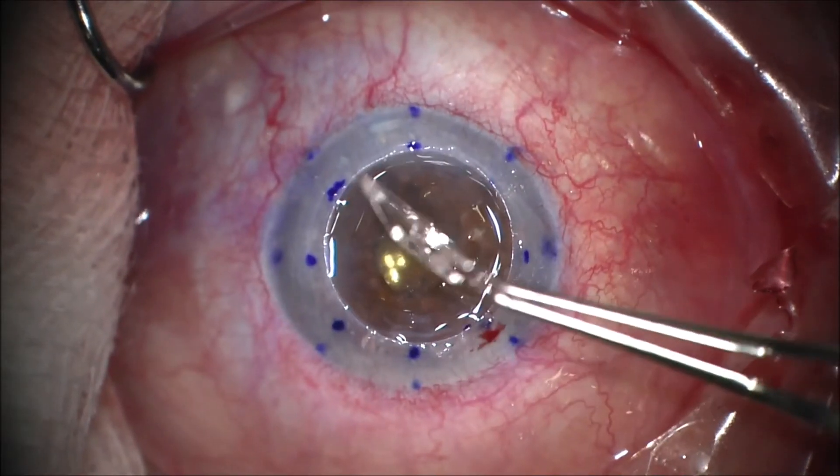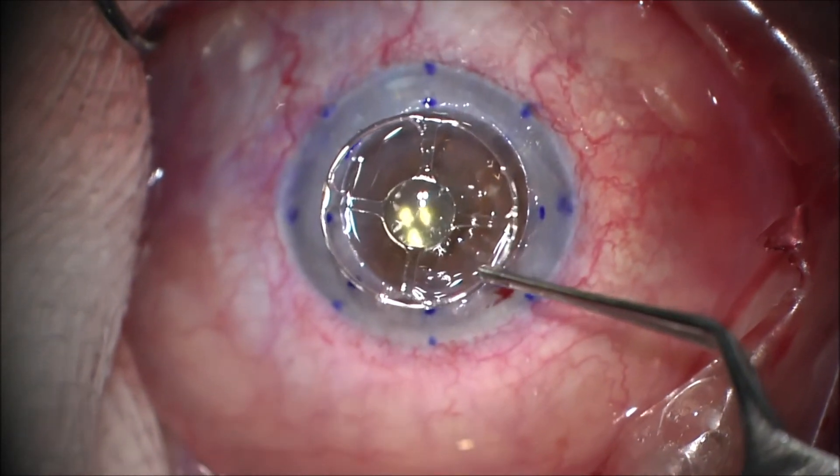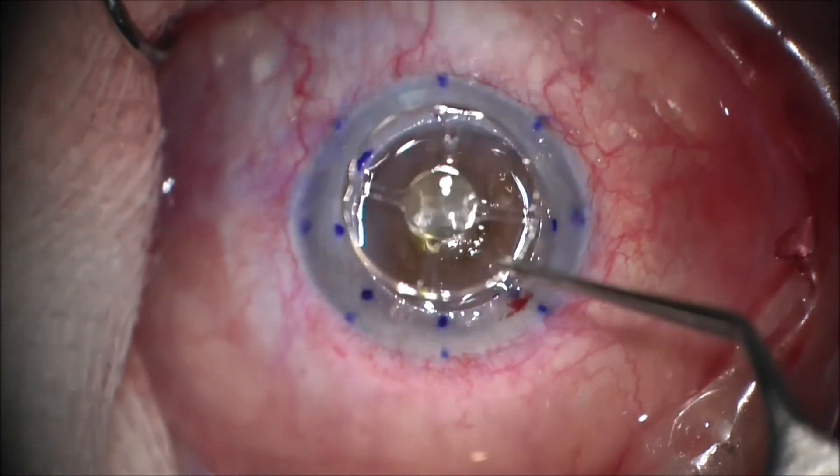In about 2017 we began the first designs of the prosthesis, and by 2018 we began to design a clinical trial that was to last two years. The endokeratoprosthesis consists of a peripheral ring, an optically neutral central disc, and four spokes joining both elements together. It is made from PMMA, and these two elements — the ring and the disc — are on different planes.